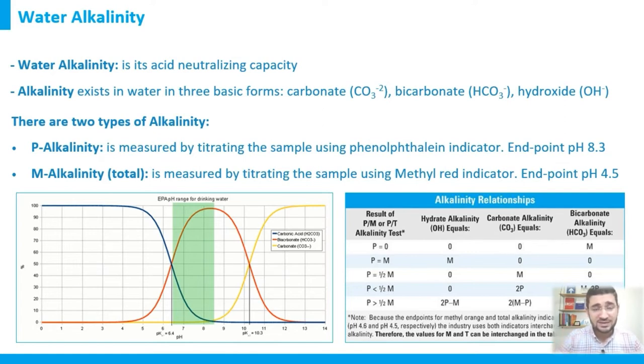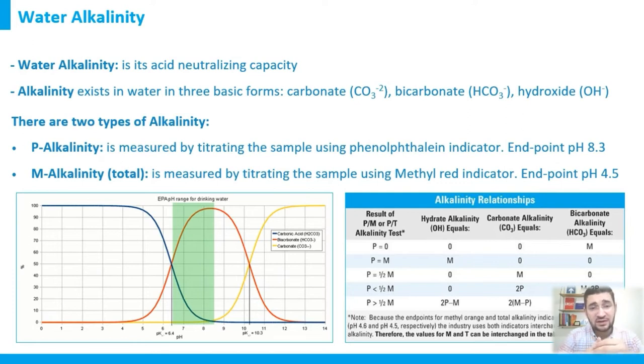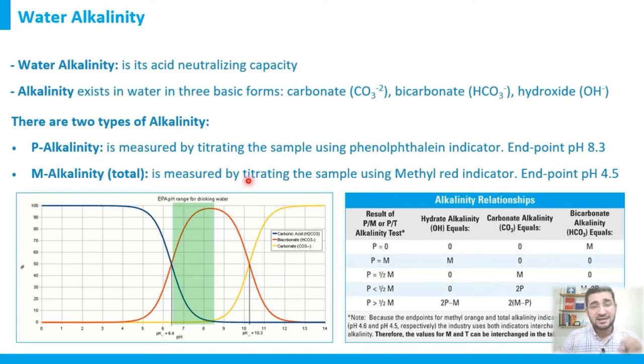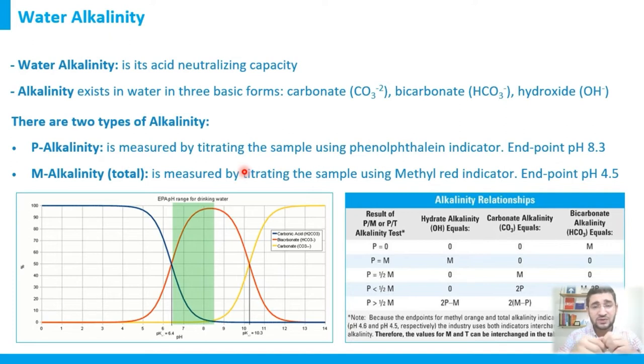There are two types of alkalinity that can exist in water. The first is called P-alkalinity, where P stands for phenolphthalein, which is the indicator used for the analysis of this alkalinity. P-alkalinity is measured using phenolphthalein color indicator, which has an endpoint at approximately pH 8.2 to 8.3.